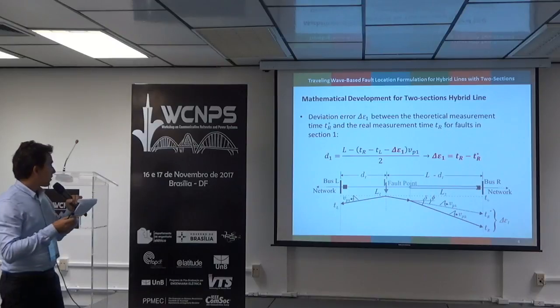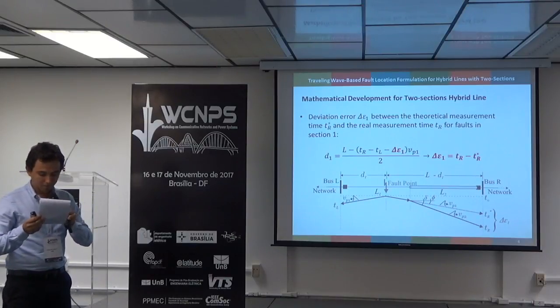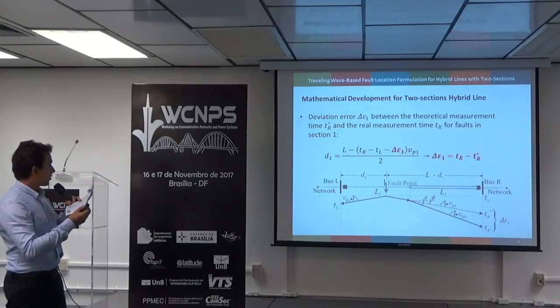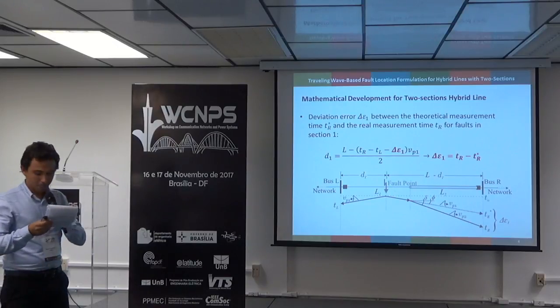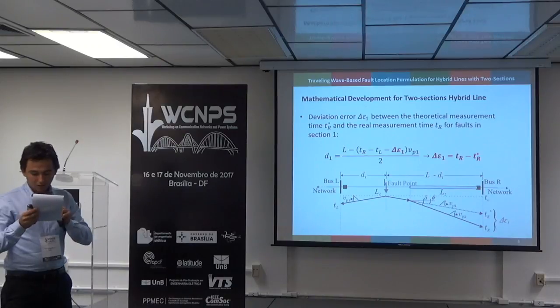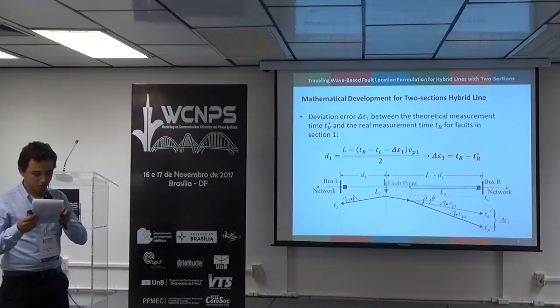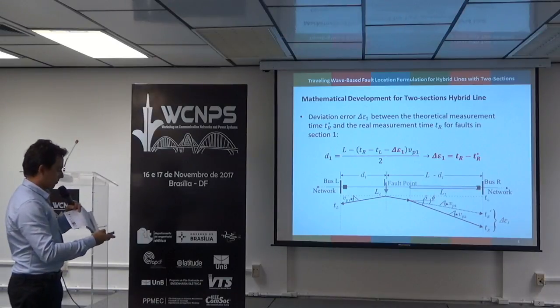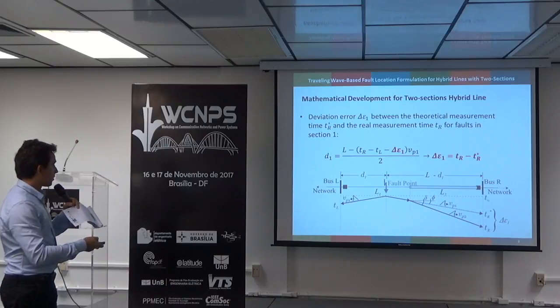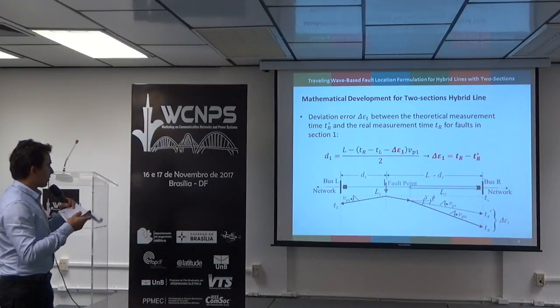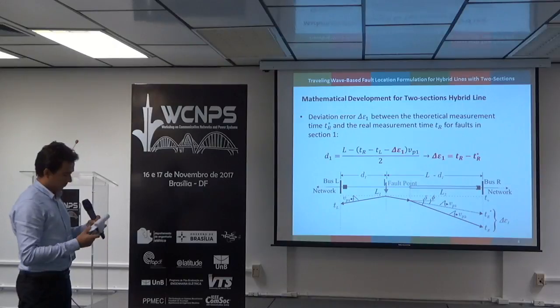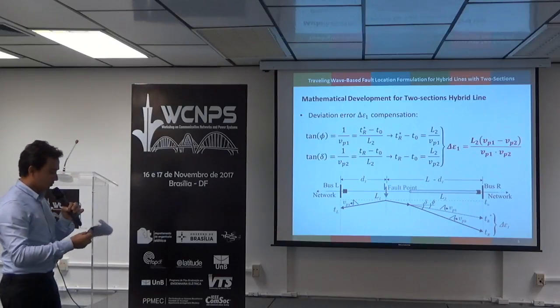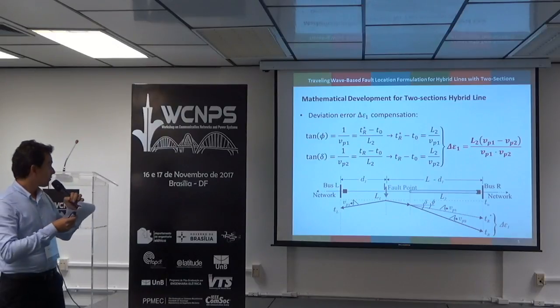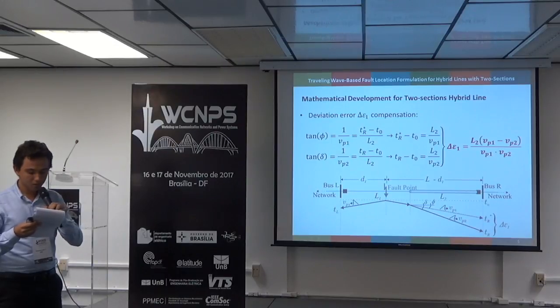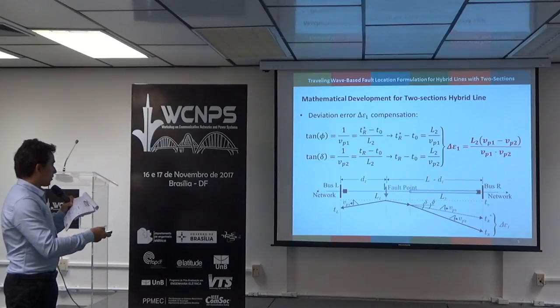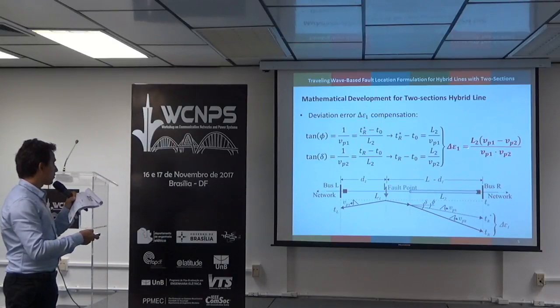Therefore, by the application of the classical method, considering faults in section 1, at this point, it's necessary to compensate the deviation error delta epsilon 1 here, between the real and theoretical, measured time. In order to compensate the deviation error for faults in section 1, by the properties of similar triangles, we can obtain the equation of the deviation error for faults in section 1.